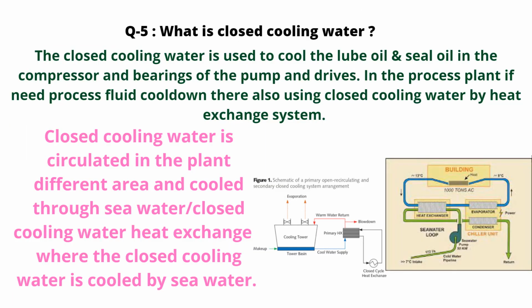What is closed cooling water? The closed cooling water is used to cool the lube oil and seal oil in the compressor and bearing of the pump and drives. In the process plant, if process fluid needs to be cooled down, they also use closed cooling water by a heat exchange system. Closed cooling water is circulated in the plant's different areas and cooled through a sea water / closed cooling water heat exchanger, where the closed cooling water is cooled by sea water.